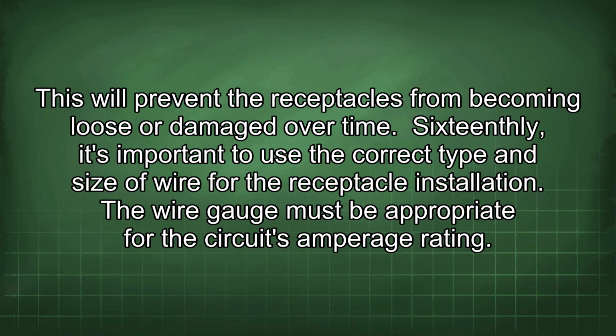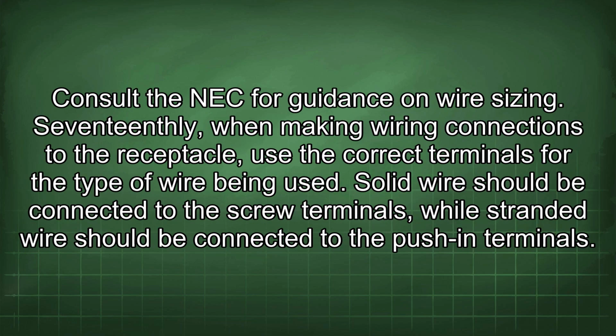16thly, it's important to use the correct type and size of wire for the receptacle installation. The wire gauge must be appropriate for the circuit's amperage rating. Consult the NEC for guidance on wire sizing. 17thly, when making wiring connections to the receptacle, use the correct terminals for the type of wire being used. Solid wire should be connected to the screw terminals, while stranded wire should be connected to the push-in terminals.